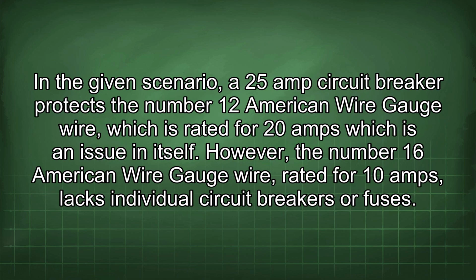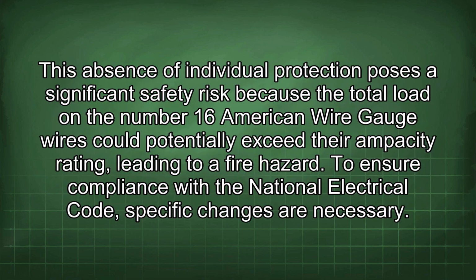In the given scenario, a 25 amp circuit breaker protects the number 12 American wire gauge wire, which is rated for 20 amps, which is an issue in itself. However, the number 16 American wire gauge wire, rated for 10 amps, lacks individual circuit breakers or fuses. This absence of individual protection poses a significant safety risk because the total load on the number 16 American wire gauge wires could potentially exceed their ampacity rating, leading to a fire hazard.